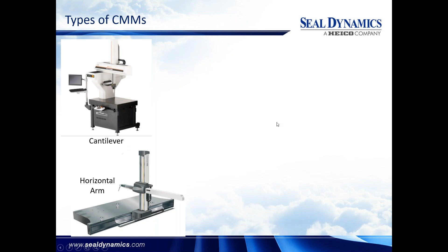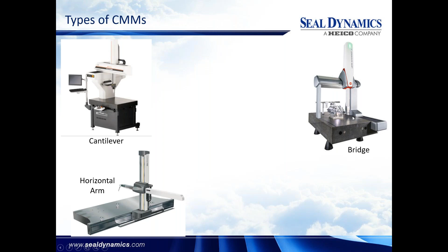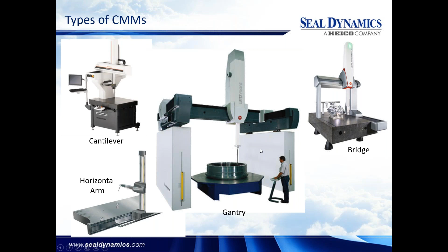The next one, the bridge, is probably the most popular and most common. It's similar to the one right behind me; it almost looks exactly like it. The bridge CMM is probably the one that you guys have in your own shops. Then, a few people see them, I've seen them actually, as a gantry. To give you a sense of size, that's a person standing there. The only difference between that and a bridge CMM is that the stands are mounted directly to the floor, typically. And obviously it's for much larger components. We had something almost as big as a gantry. It was actually the largest bridge that you can make. We would inspect the 60-inch turbine center frames for the GE90 engine on it, in a former life, that is.